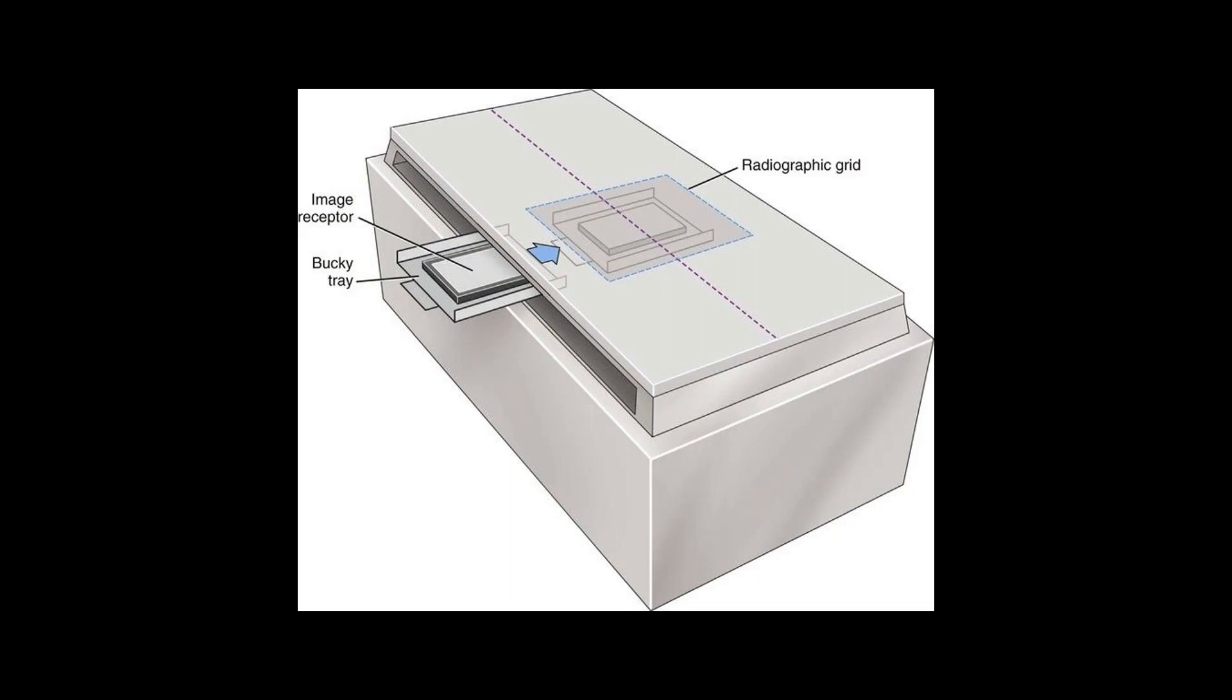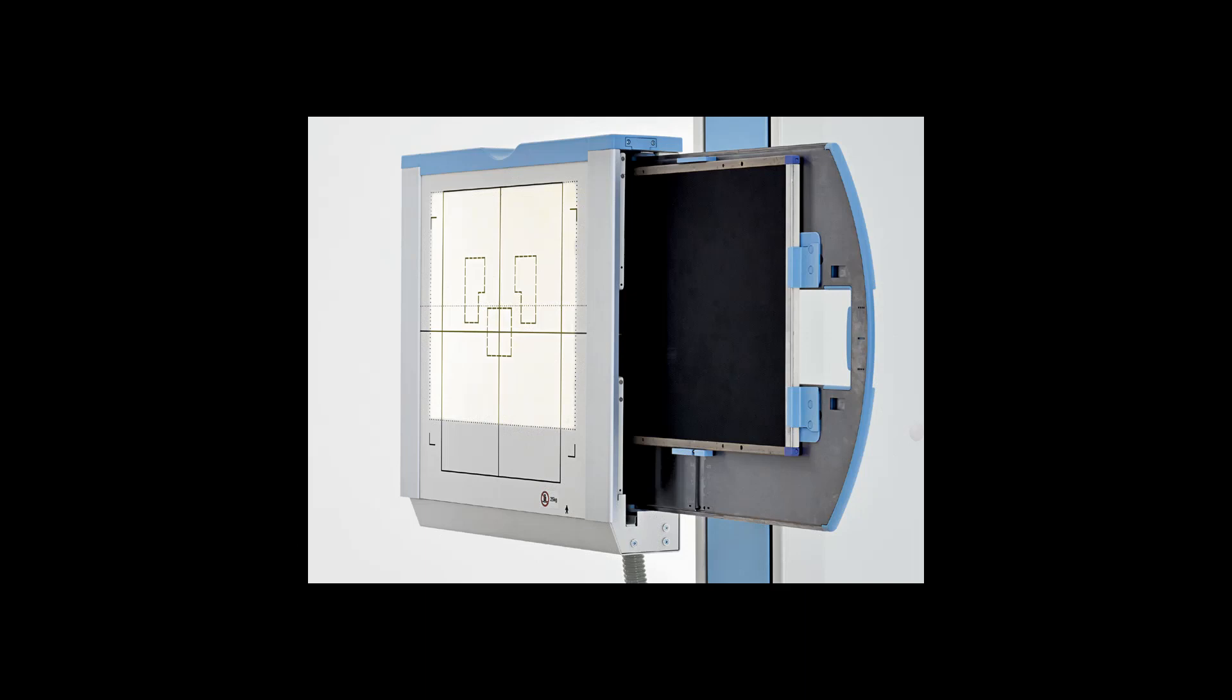The grids are placed between the patient and the film cassette. Meaning, if you have an x-ray table, the grid is placed directly under the table board. Or if you shoot x-rays upright, like chest x-rays, the grid is hidden behind the wall board.